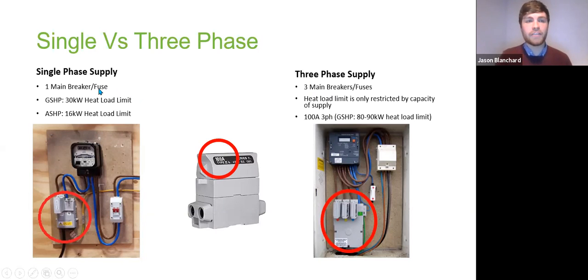Most people in the UK will have a single phase supply, and the majority of domestic homes will have 100 amp single phase supply, which will be denoted by a sticker, or potentially on the older ones, sort of plastic engraving of 100 amps on the breaker. These are very much rules of thumb, and I know that Rona will probably go through a bit more detail, but the limitations of your supply, if you have a single phase supply, you're looking at up to around a 30 kilowatt heat load for a ground source and around a 16 kilowatt heat load for an air source heat pump on 100 amp sort of domestic supply. 3-phase supply, well, the sky is kind of the limit. It depends very much on your amperage at that point, but the majority of heat pumps will run quite comfortably off of 100 amp 3-phase supply.